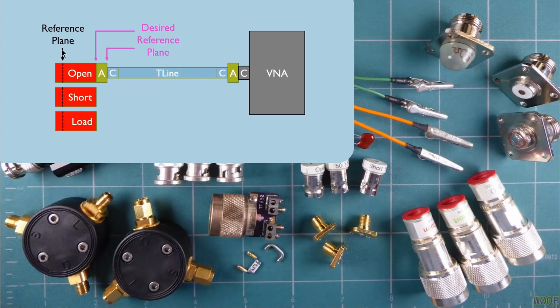And when we're done, the VNA is calibrated at this reference plane right here. However, this reference plane is not at an interface you'll ever be able to use, because when you remove the open short loads, you're left with either a boundary right here, or if you remove the adapter, you're left with a boundary right here. One of these two is going to be where you desire the reference plane to be. However, the reference plane from the point of view of the VNA is out here. So what are we going to do about that?